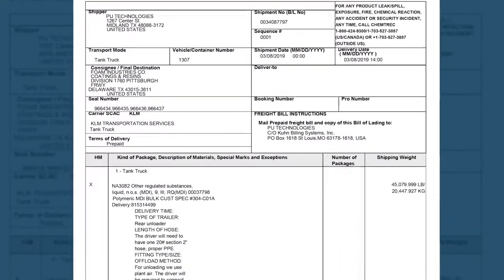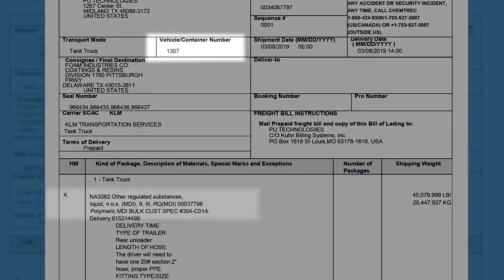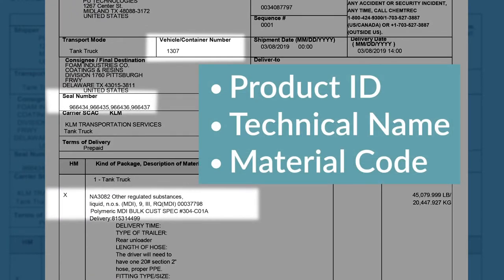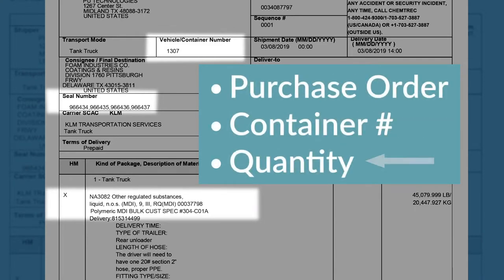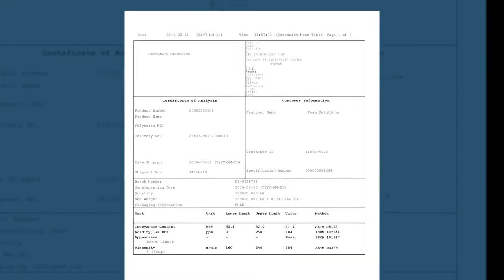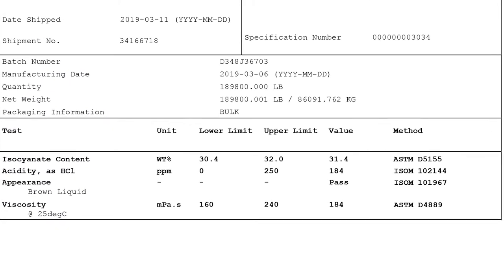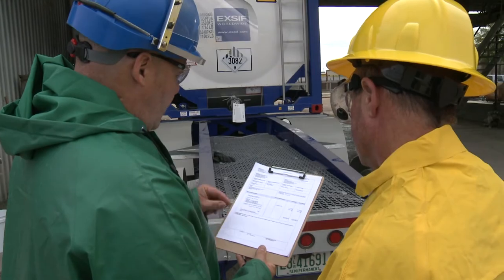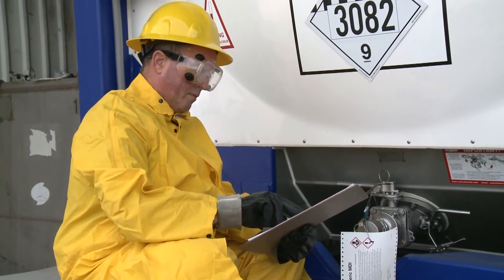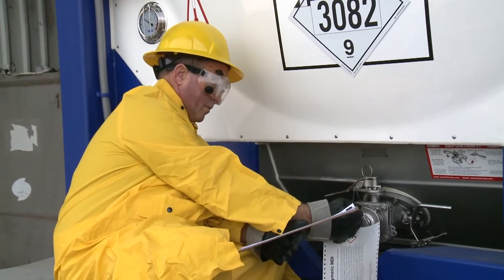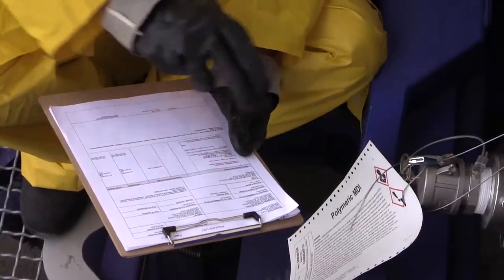Verify the driver's paperwork to validate trailer number, product identification tag, security seals, that the material being received is the correct MDI product, and that the weigh ticket shows the quantity being delivered to help ensure the volume of the delivery will fit the storage tank. Review the values on the certificate of analysis to determine whether the product meets required specifications. Once all paperwork is verified, check the tank container to make sure the numbers on the security seals match the seal numbers shown on the paperwork.